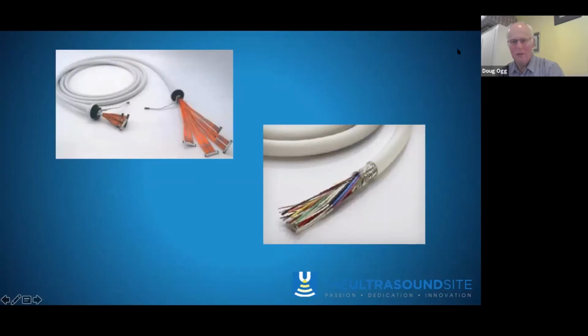With the broken apart cable, that's it. That one. You can see on that there's actually some shielding surrounding that cabling as well. Now, when you run over a cable with your ultrasound scanner, which happens not infrequently, you are compressing all those little cables together. They get moved around, and they're small. They're not that strong, and they can get damaged. And that damage will build up progressively.